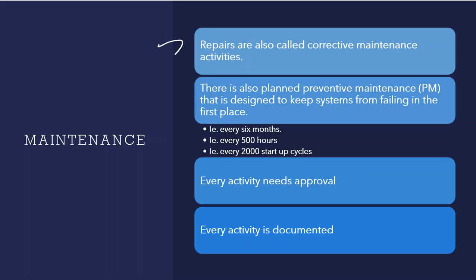So these repairs are going to be important. If we don't look at our maintenance schedules for, say, that chromatography column, at a certain point it's going to go bad. And if that column goes bad, unless we have a backup, it is out of commission and stops everything from that point, and we cannot allow that to happen. So maintenance, flushing, cleaning, and changing parts are drastically important.